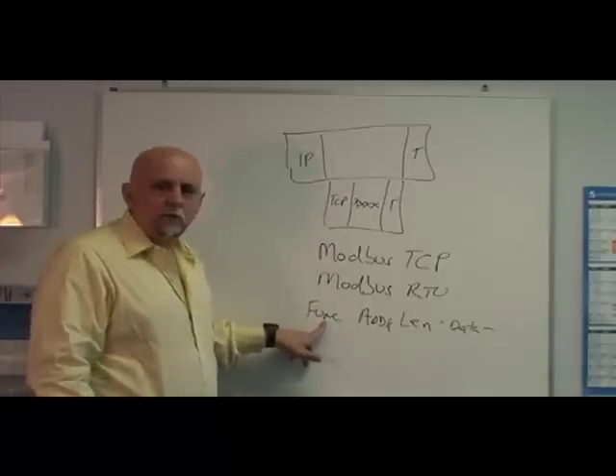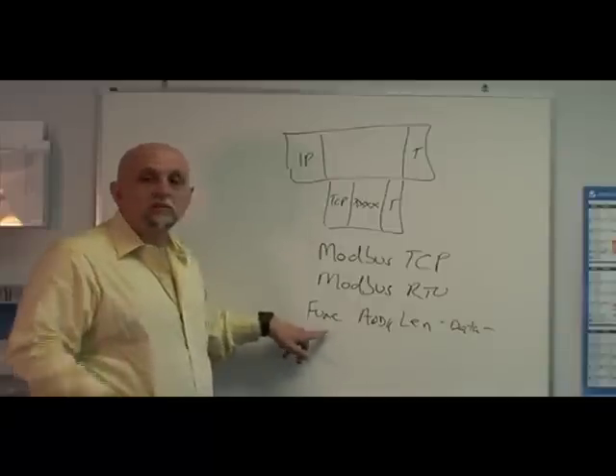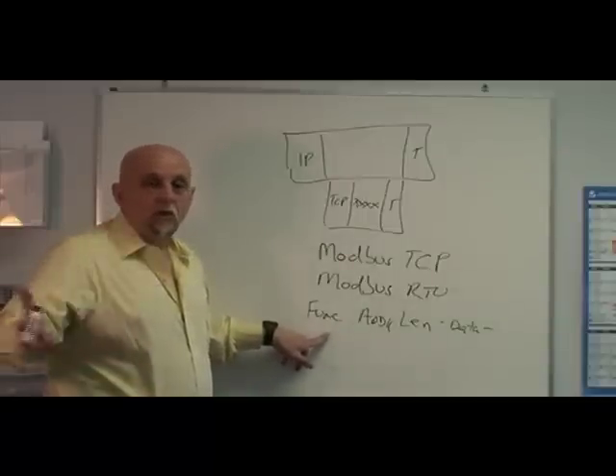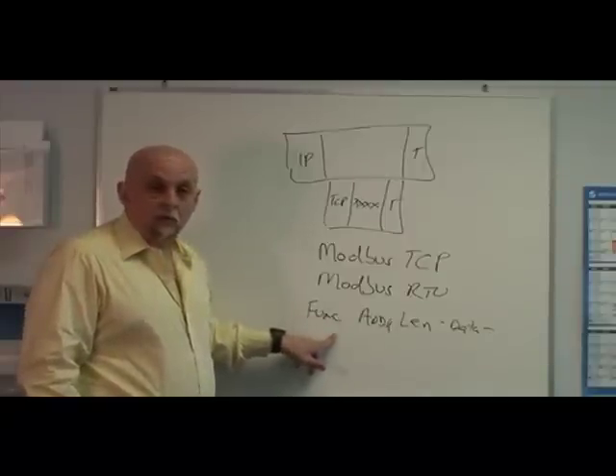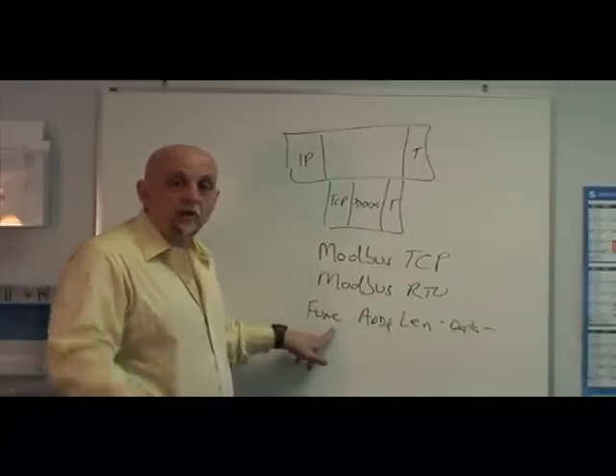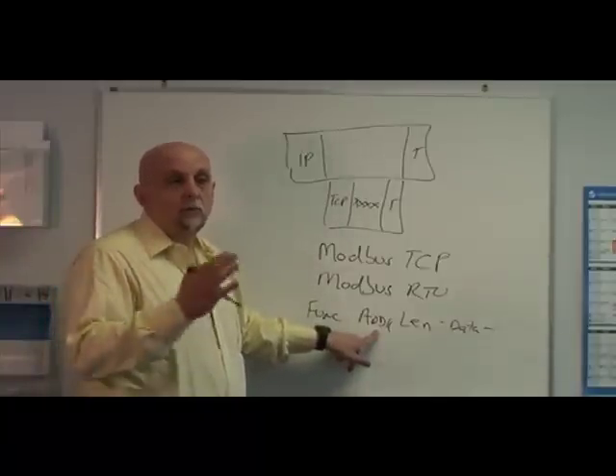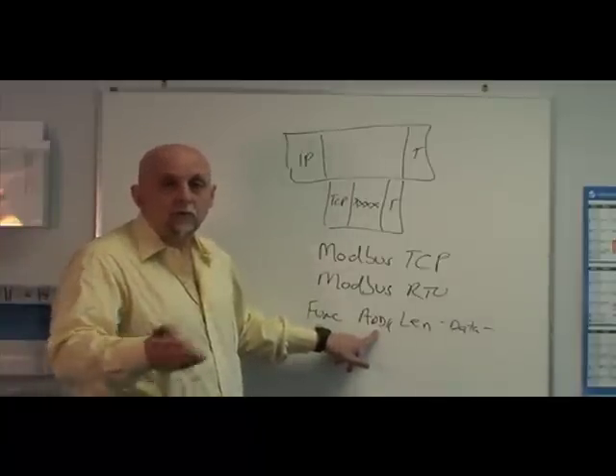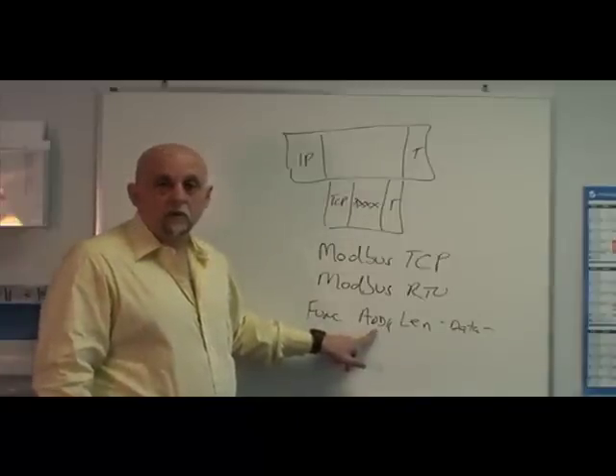So then he just sends back a message saying, well, here's an error code because I don't support that. Or he says, oh, they want to read holding registers. Oh, I've got holding registers. So they look at the address and say, man, that address is outside the bounds. I'm only supporting addresses 100 to 200. They want to read address 300. Well, can't do that so send back an error code.